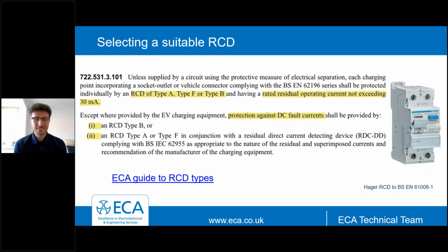So yeah, selecting a suitable device, consulting the manufacturer's data is going to be critical to this process. It's either going to need to be a dedicated type B or a type A or a type F in conjunction with an RDCDD device, and getting that clarity from the manufacturer is going to assist with the selection of that equipment.